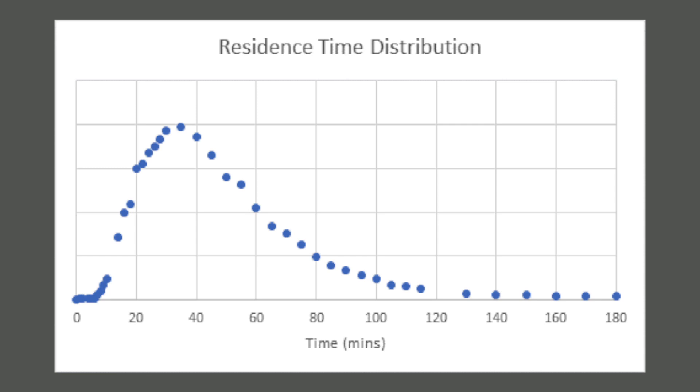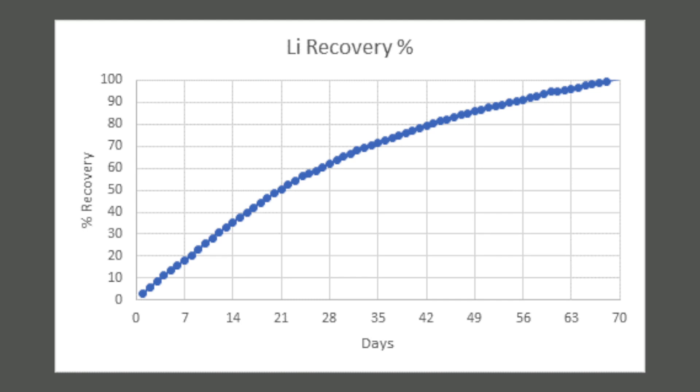Accounting for the flow, and using calculation methods described by Octave Levenspiel — that's Chemical Reaction Engineering, 1974 — the flow and concentration can be converted into a residence time distribution curve. Recovery curves can also be created. Visual and statistical analysis of the data in the graph provides an assessment of the plug flow characteristic, the short circuiting, and the active volume.